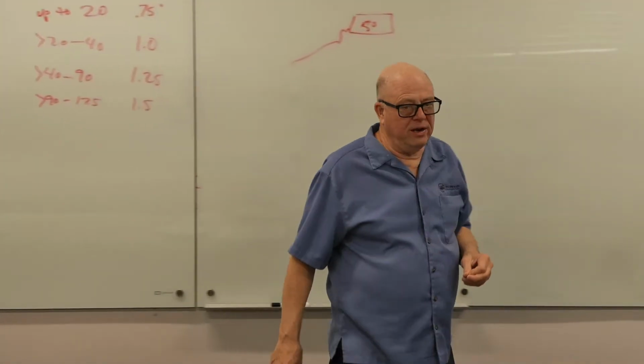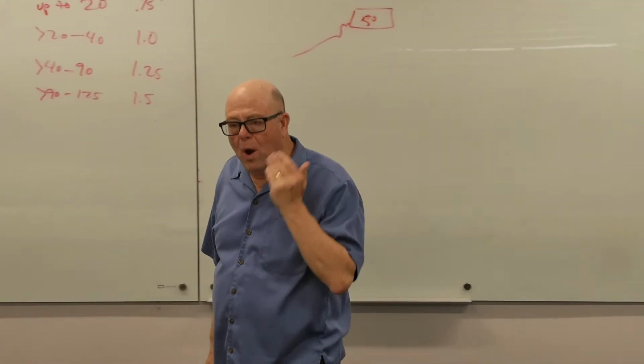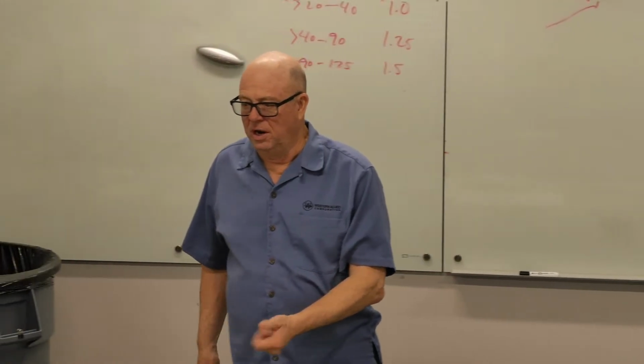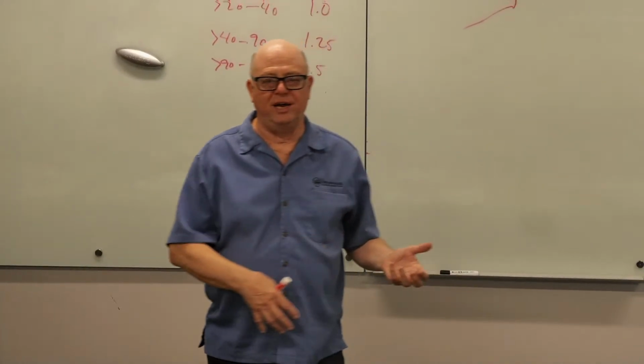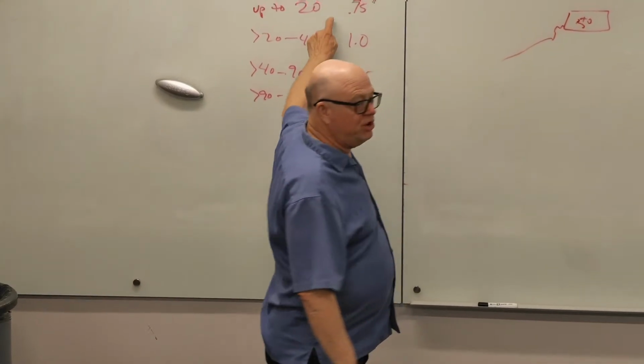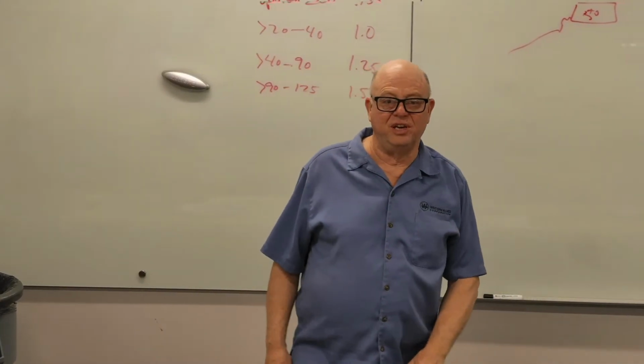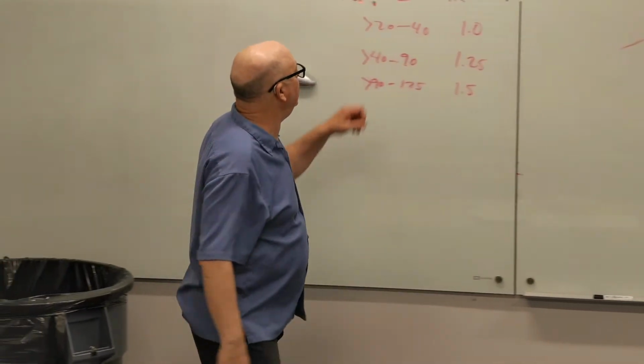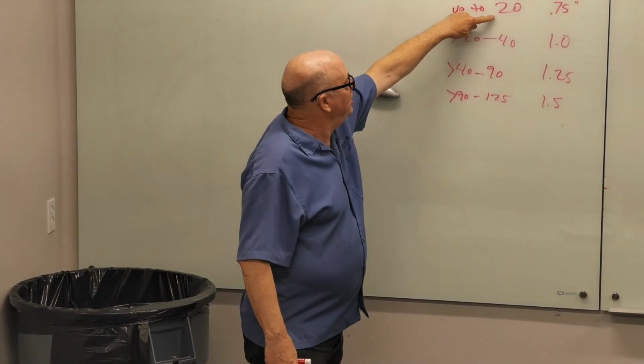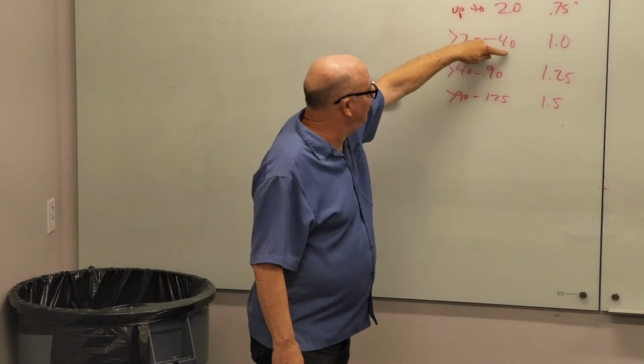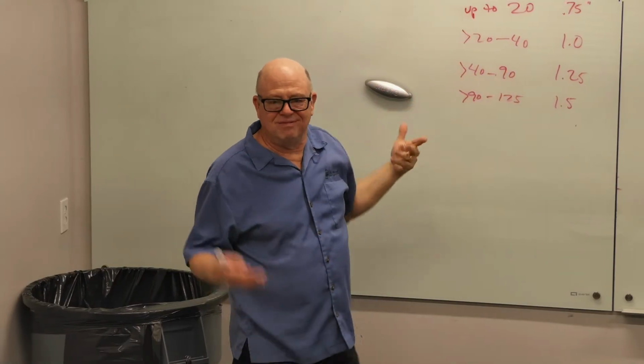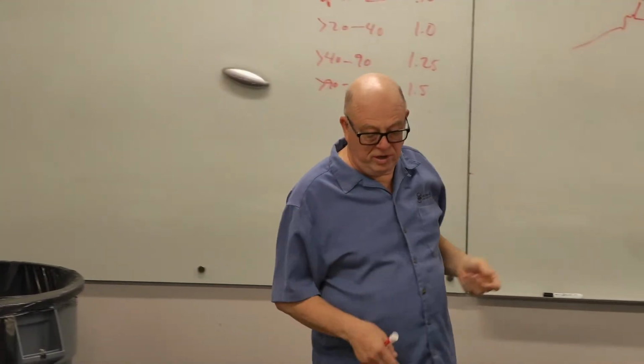Only reason I bring that up is that when you do a retrofit, if you're going to change equipment size, remember to check the condensate drain line, especially if you're breaking sizes. You're going from a 20 to a 25, or you're going from a 40 to a 50, okay? It's one more thing you got to check.